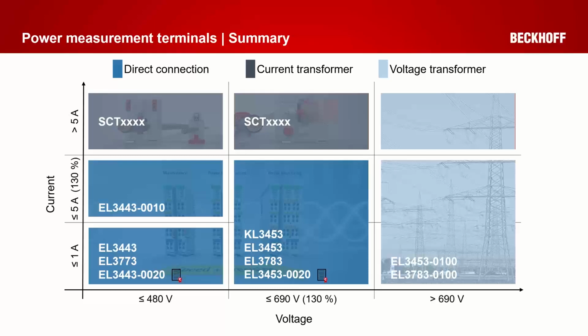Therefore, we need extra voltage transformers. For this, as I have explained, we have for all of our terminals also a 100 volt variant terminal available. And you can see here, for all three-phase systems, we have the corresponding terminal. Also, we have some terminals, for example, the EL3773 and 3443. They also allow DC voltage measurements.